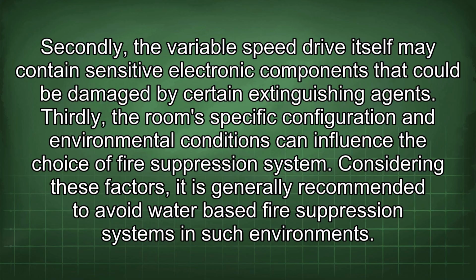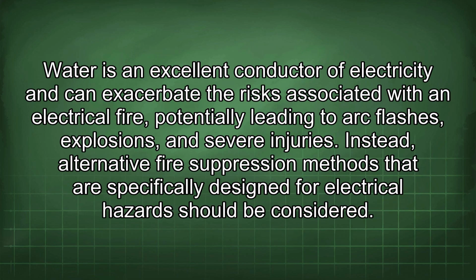Considering these factors, it is generally recommended to avoid water-based fire suppression systems in such environments. Water is an excellent conductor of electricity and can exacerbate the risks associated with an electrical fire, potentially leading to arc flashes, explosions, and severe injuries. Instead, alternative fire suppression methods that are specifically designed for electrical hazards should be considered.